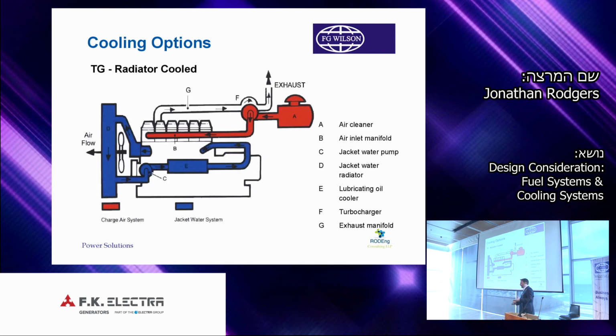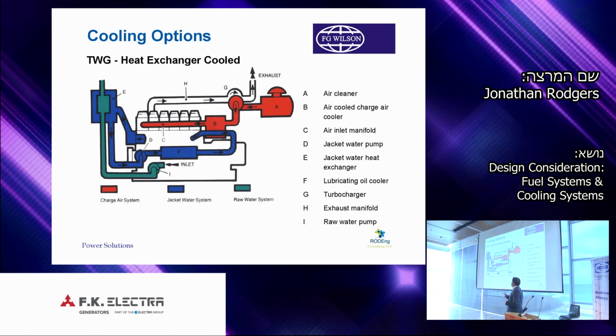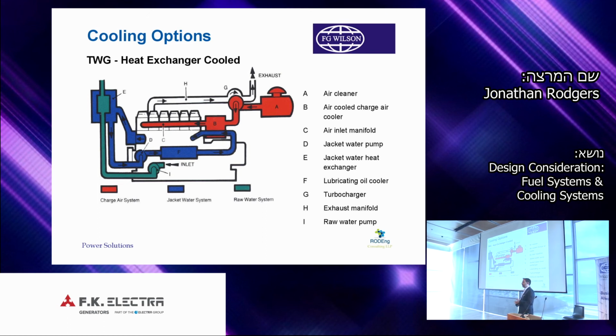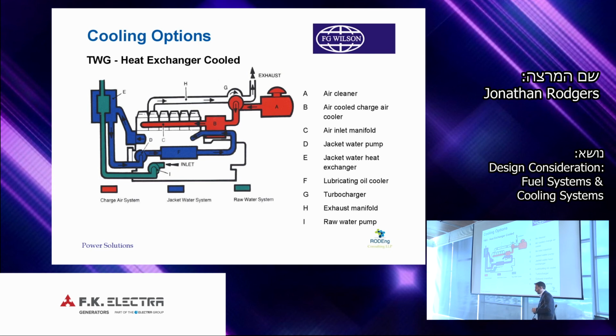We also have TG, which is on some of our smaller engines, and this is really where there's a higher flow through the charge circuit, and it's discharged to ambient air and to exhaust. So it's controlled through the turbo selection and turbo sizing, and the radiator core has then one single circuit. We may have heat exchanger cooling, where we're taking the heat onto another cooling source, a cooling tower, a remote radiator, maybe another form of seawater cooling.